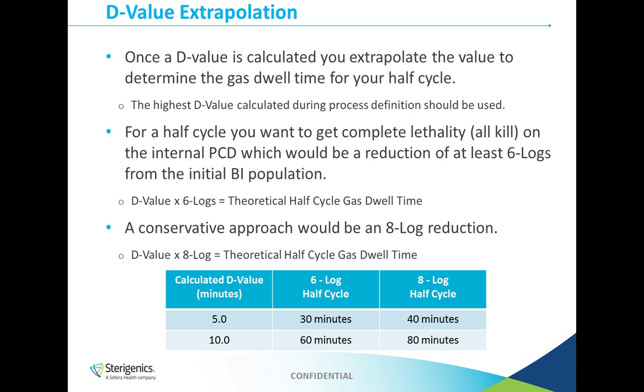Now a more conservative approach is to use an 8-log reduction, and that's where you take the D value, you multiply it by 8, and you get the theoretical half cycle gas dwell time. So for example, if you run your fractional runs and you get two different D values, let's say 5 minutes and 10 minutes, you're going to want to use that 10 minutes. And with that 10 minutes for a 6 log, you would have a gas dwell time for your half cycle of 60 minutes. Using 8 log, you're going to get an 80-minute exposure time for your half cycle.